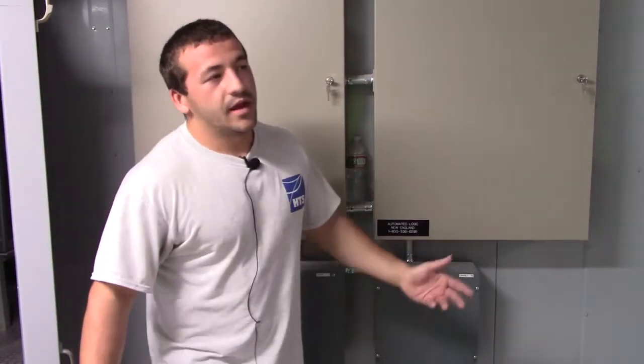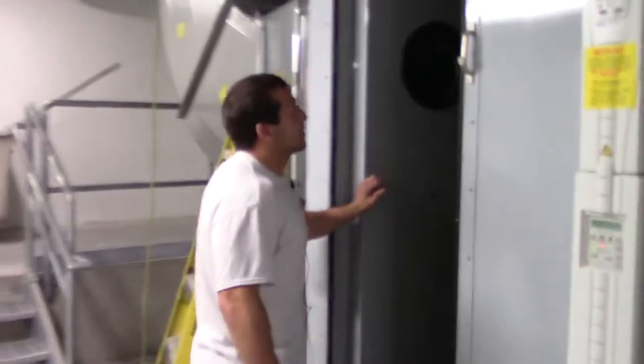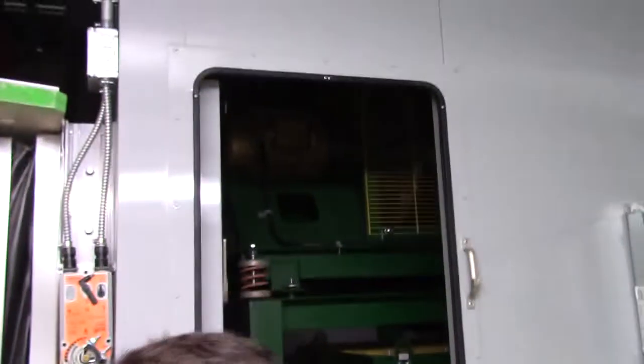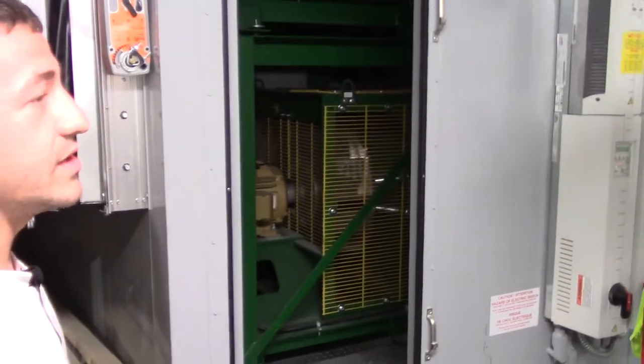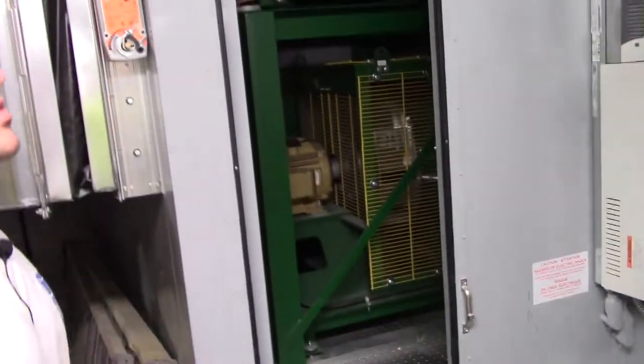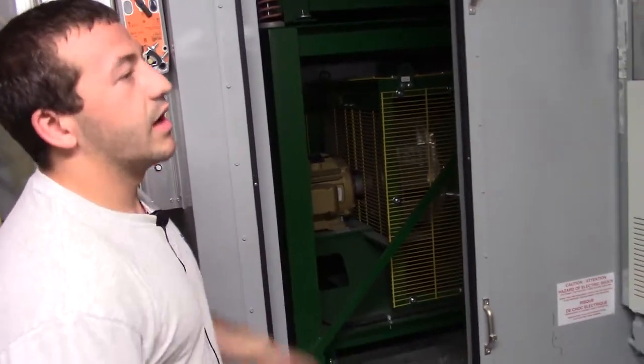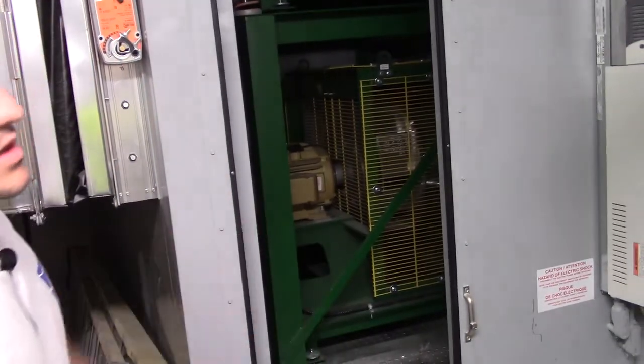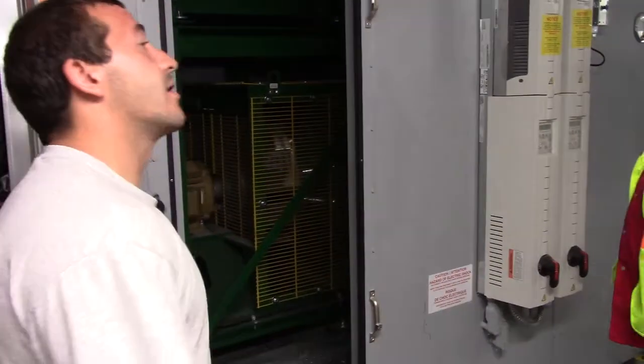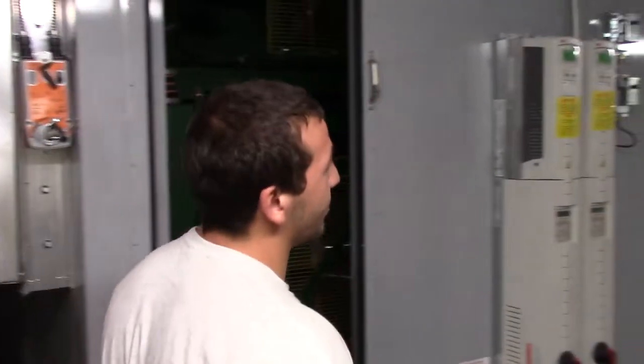and then just control it through the BMS system. And then for maintenance purposes, I'll go through the unit first and show you where everything is. You've got your return and exhaust fans right back here. You've got grease fittings on both of them. So grease them every time you're doing maintenance on it, whatever you see that this unit needs. Once you start getting into it, you'll know how dirty the filters get, how quick, and how often you want to do it. Probably grease it and do the maintenance on it every 1 to 3 months, something along those lines. You'll get a better ballpark once it hits that point. They're all on isolated springs to try to reduce vibration and noise.